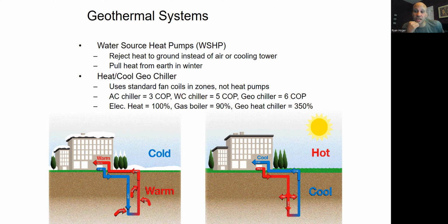We have some projects like that in downtown Chicago, where there's buildings right on the river, and they have a permit from the EPA to suck river water into the basement of the building, run it through the condenser side of the chiller, and then dump it right back into the river. I think the EPA only gives so many of those permits because now you're warming up the water temperature of the river over the course of time, which obviously changes the way things are for fish and stuff like that.